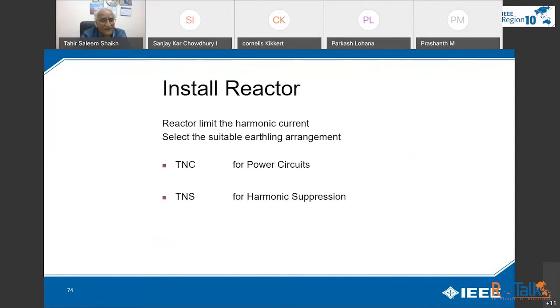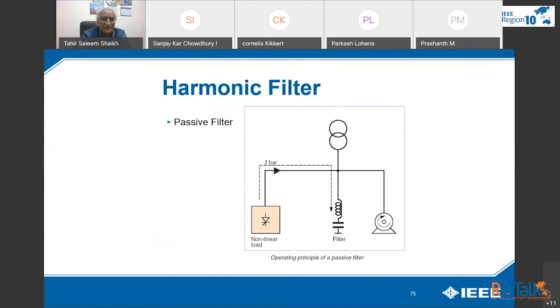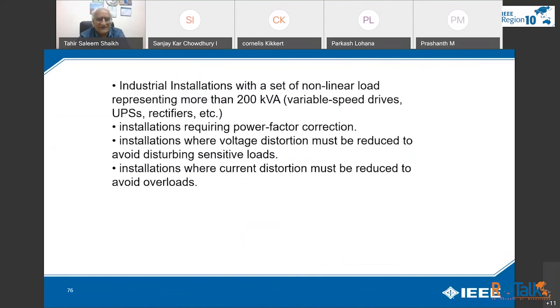If you install a filter, this is very expensive. What filters are, you can see over here. This is a passive filter. The reactance and capacitance are connected to the non-linear load, and this non-linear load noise is filtered out through ground, and the pure sine wave goes to the linear load. A passive filter is used in industrial installations with a set of non-linear loads representing more than 200 kVA, such as variable speed drives, UPS, etc. It is used where the installation requires power factor correction, where voltage distortion must be reduced to avoid disturbing sensitive loads, and where current distortion must be reduced to avoid overloads.